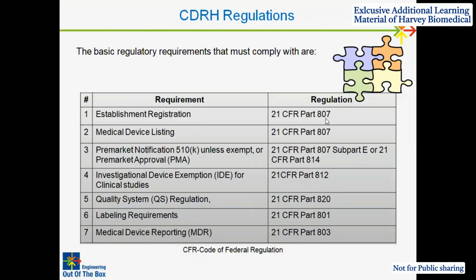Check 21 CFR Part 807 and you will get the establishment registration requirements. Accordingly, you can gain detailed knowledge if required. Quality system, as I told, the quality management system regulation, is 21 CFR Part 820. Labeling requirements are 21 CFR Part 801. Medical device reporting is 21 CFR Part 803.